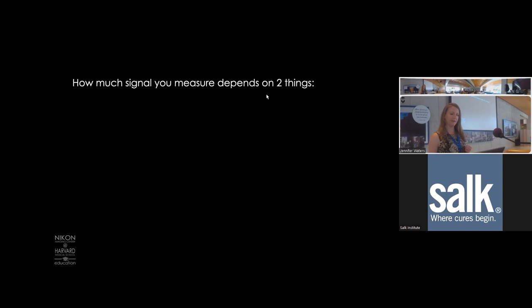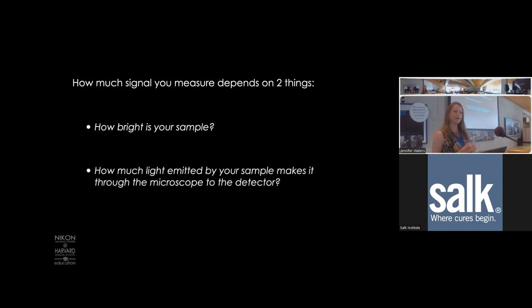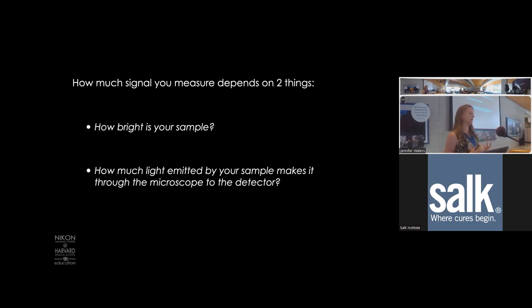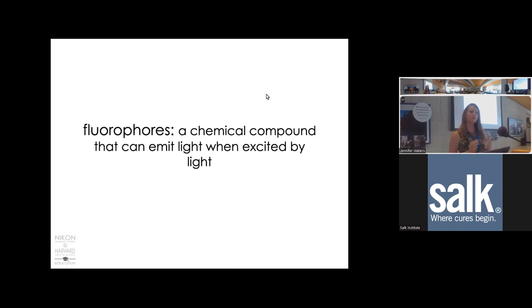How much signal you measure depends on two things: how bright your sample is—how many photons it's actually emitting—and how much of that light actually makes it through your microscope to the detector. How bright your sample is depends largely on your fluorophore. The photons you detect as signal come from fluorophores as a result of the fluorescence reaction. Fluorophores are chemical compounds that can emit light when excited by light.